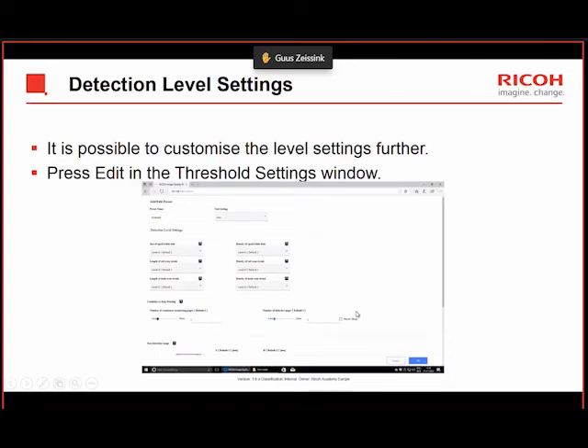This is another screen that's available under edit. If you set your threshold level to level 2, you can also change settings inside that detection level to customize it. This is also available for the customer, so you can change other things like size of speck or white hole. You can change that in there and change the levels. So you could, for instance, have it set to level 2, but have this specific fault set to level 1. So you can customize it even further.